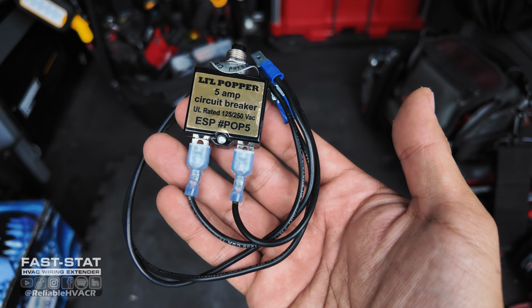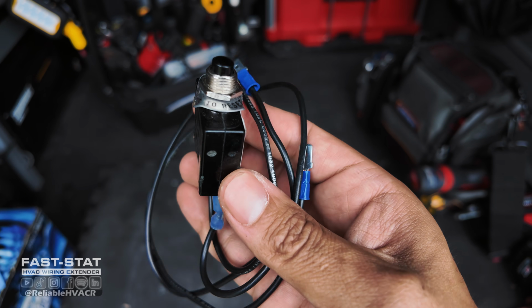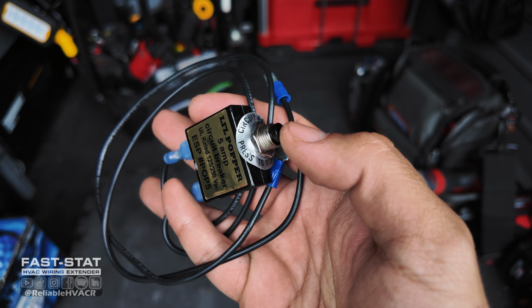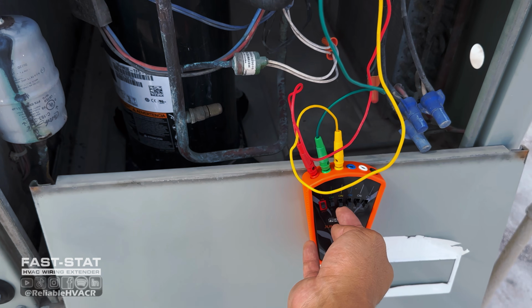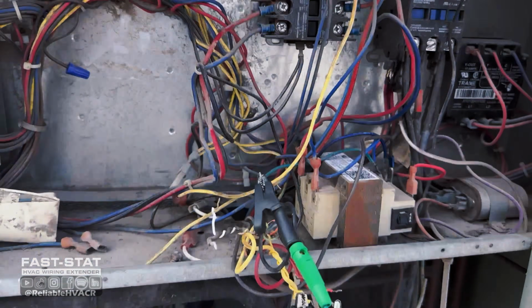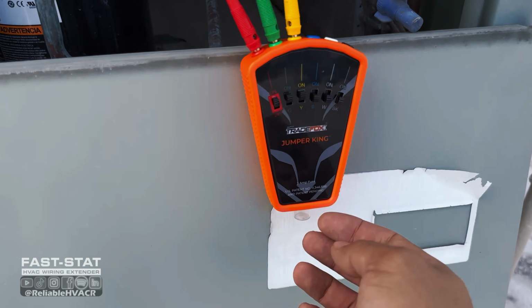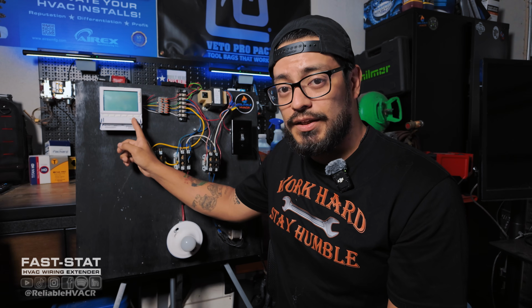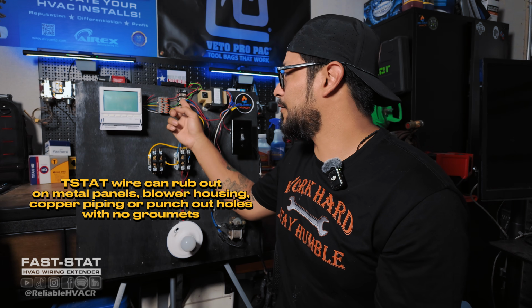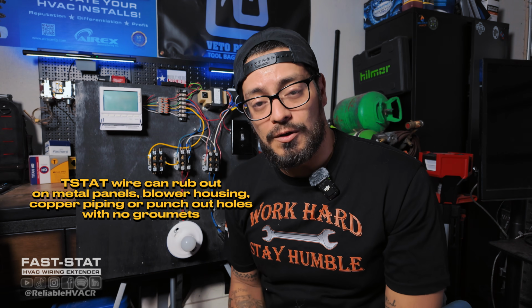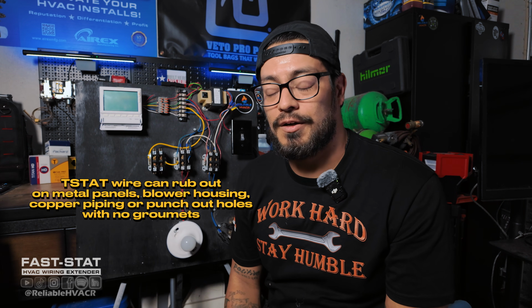Now, if that fuse is popped, there are a few tools that you can use, such as a popper. It's typically available in like a 3 amp or 5 amp, and it's resettable. So typically you hook that up in between where the fuse was supposed to go, and you reset it, turn the system on. I would start with setting the thermostat to fan only, make sure your blower comes on. If it pops immediately, you know that from green to the blower motor, there is a short somewhere.